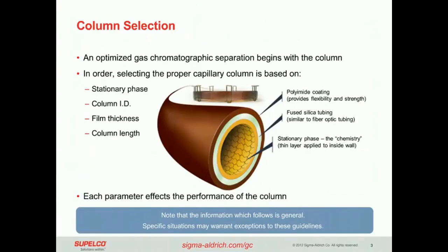GC columns have a coating of polyimide on the outside that gives it the brown or orange hue. That's really designed to give the fiber optic tubing the flexibility and strength because we want to coil these into a specific diameter to fit into the instruments.